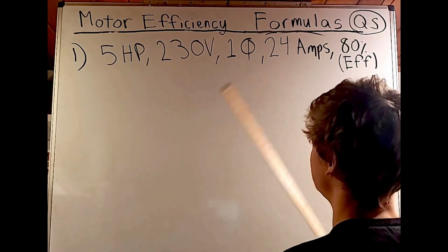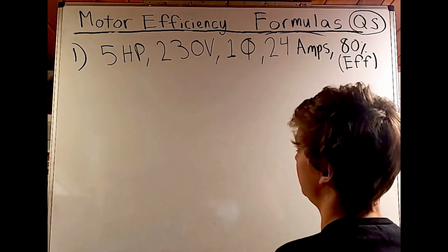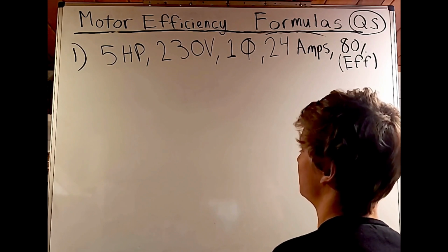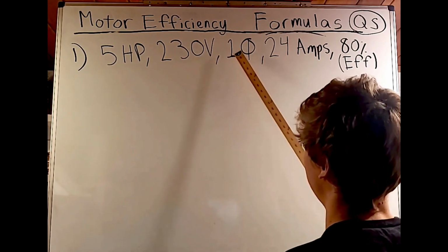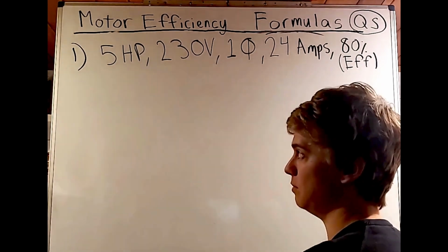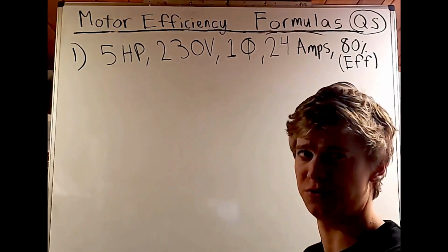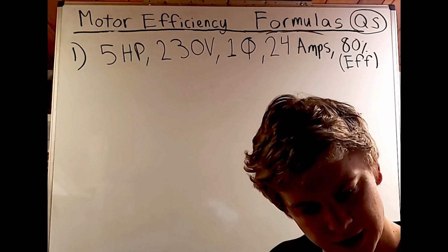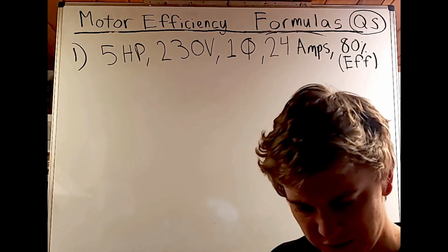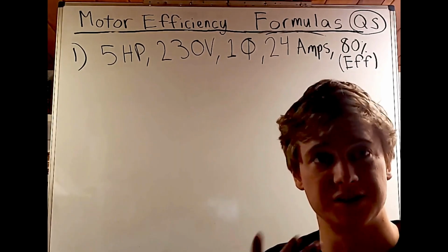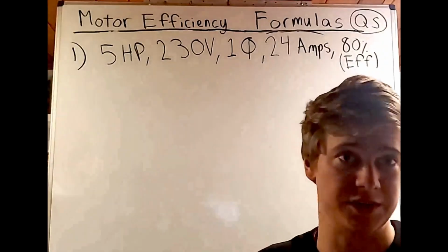Another thing, we have single phase, but we wouldn't really need to know that unless we didn't have certain information. Like if we had our horsepower and our voltage and we had our single phase, we could go to the motor table. I think it's 430.248. And yeah, it is for the alternating current single phase, 430.248. And then for 3-phase, you have 430.250, just in the same opening, next page over on the right page.